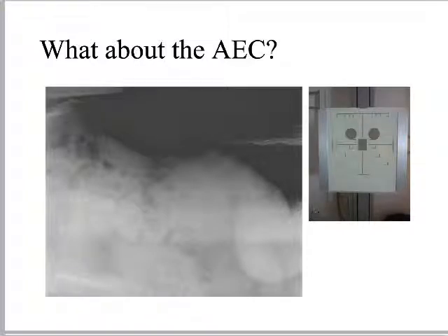So, the first rule of using an AEC is don't do what this technologist did here on this decubitus view. They activated the automatic exposure control. They either selected the wrong panels or the patient was just misaligned, so that it looks like an underexposure, overexposure. I can't tell exactly what's going on here, but the automatic exposure control probably continued to expose because it hadn't yet gotten all the ionizations that it wanted, right? So we have these burned out lungs, a whole lot of scatter inside of the abdomen, which is exactly what we don't want on this image.